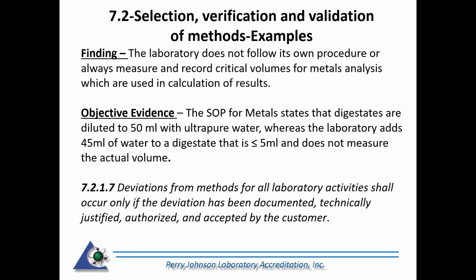Here's another example under 7.2, where the laboratory does not follow its own procedure or always measure and record critical volumes from metal analysis, which are used in the calculation of results. The issue we found here was that the SOP for metals states that digestates are diluted to 50 milliliters with ultra-pure water, whereas the laboratory adds 45 milliliters of water to digestate that is less than or equal to 5 milliliters and does not measure the actual volume. So here we found a violation of 7.2.1.7, where there were deviations from a method. And if they do deviate, they have to document why.